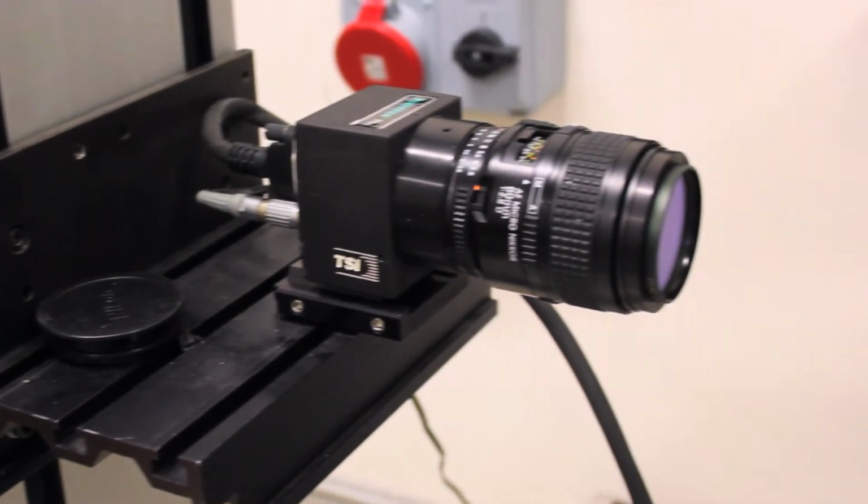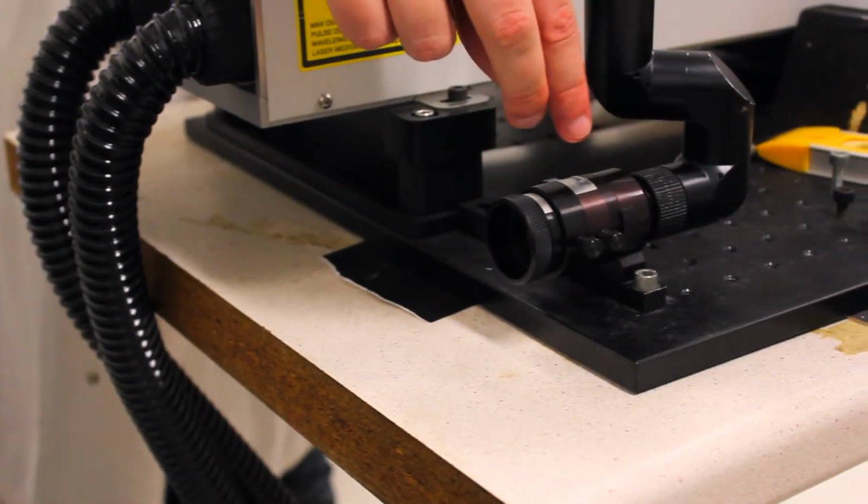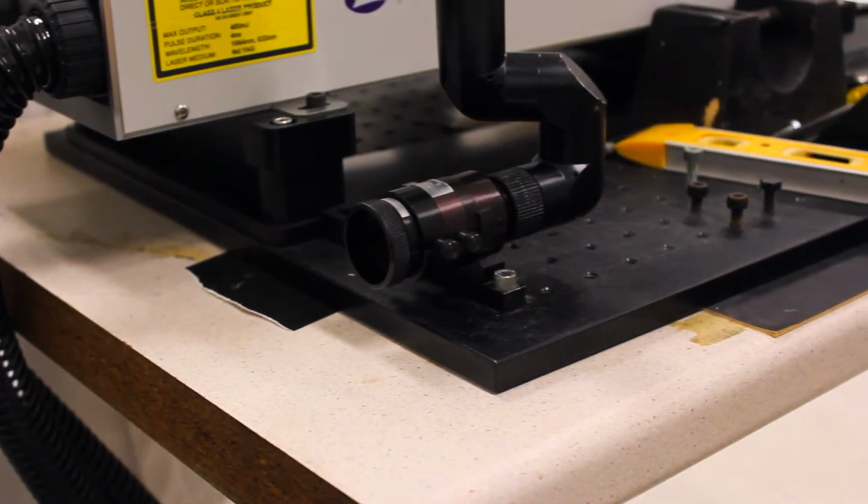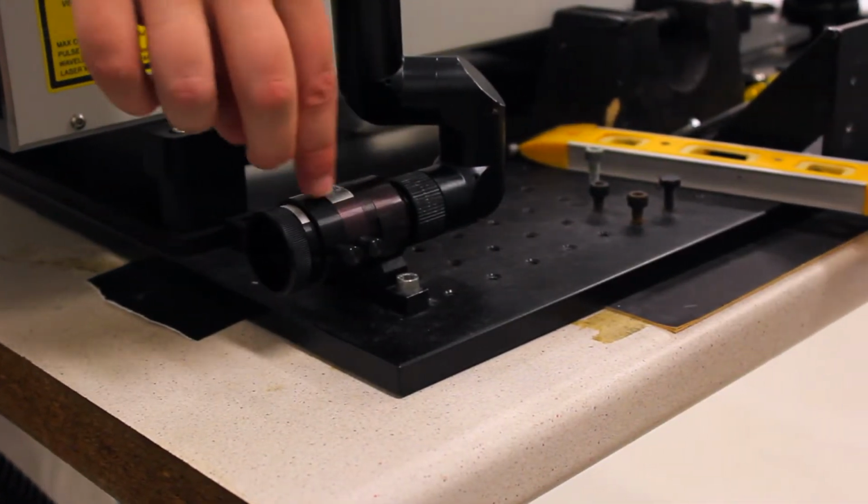Principles of particle image velocimetry. It's a method to view flows within vessels, and it works a little like a speed camera. You take 2 images and track the location of a particle, and by knowing how far it's moved over a set time, you can work out the speed at that point. There's a laser synchronized to a computer and to the camera, and this fires 2 pulses. It takes 2 pictures, and through tracking where different particles are, we get a full velocity field for the vessel.